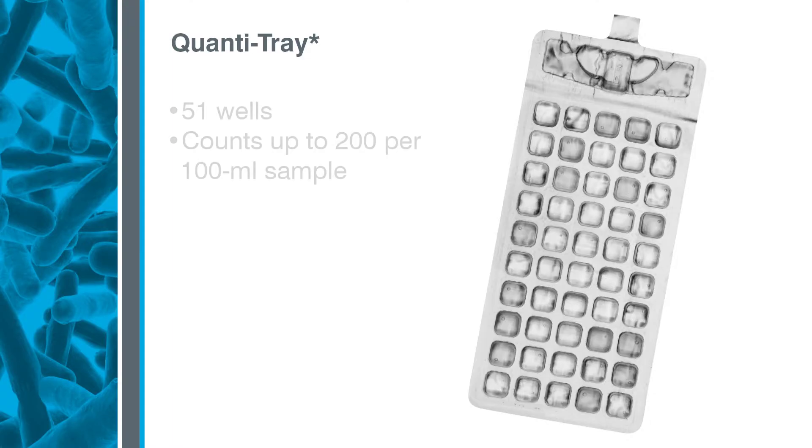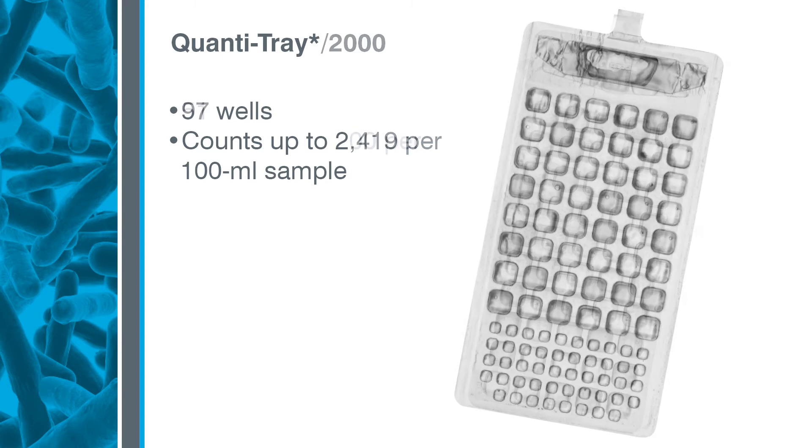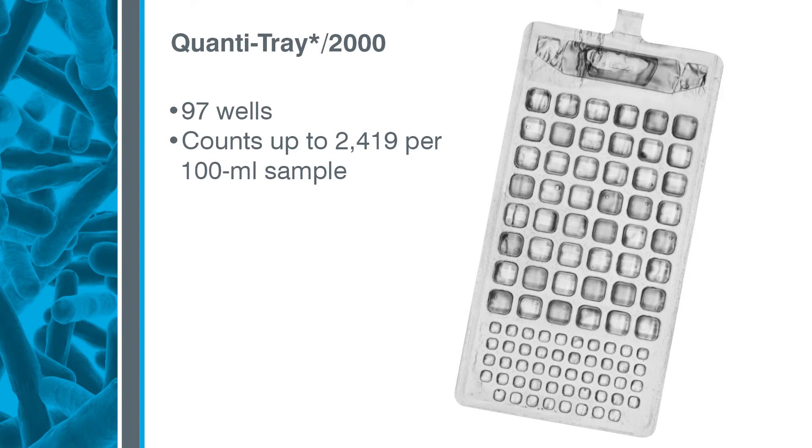IDEXX offers two sizes of Quantitray. Both work with the Quantitray sealer. The standard Quantitray is a disposable 51-well tray that provides counts up to 200 per 100ml sample without dilutions. The Quantitray 2000 is a disposable 97-well tray that provides counts up to 2,419 per 100ml sample without dilutions.